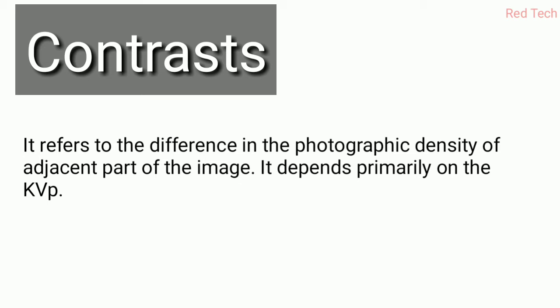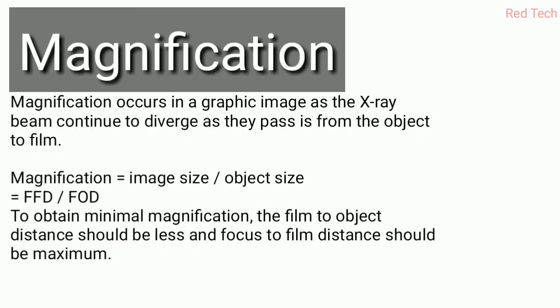The next point is magnification. Magnification occurs in a radiographic image because the x-ray beam continues to diverge as it passes from the object to the film. Magnification can be calculated by dividing image size by object size. To obtain minimal magnification, the object-to-film distance should be as small as possible, and the focus-to-film distance should be maximum.